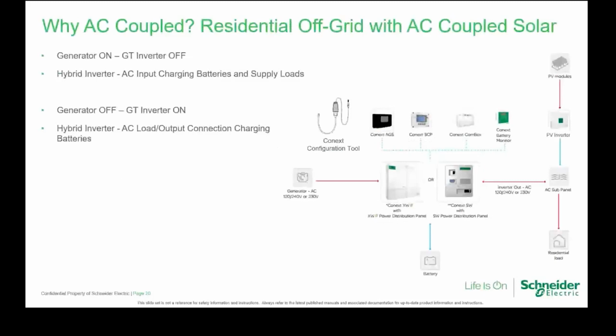When you're off-grid with AC coupled solar, we've got the generator on instead of the grid. You've got to have the generator on with the grid-tied inverter off. You cannot have both on at the same time, otherwise you're going to start backfeeding the generator and you might damage your generator. The hybrid inverter can do AC input charge to the batteries and can then supply the loads. When you've got the generator off and the grid inverter is on, this one can then do direct power to the loads. It can also charge the batteries.